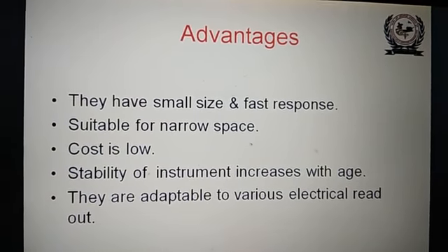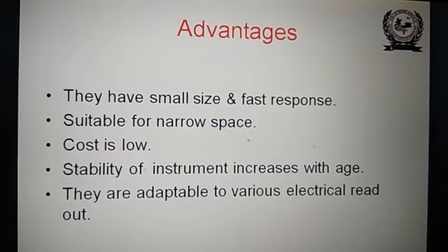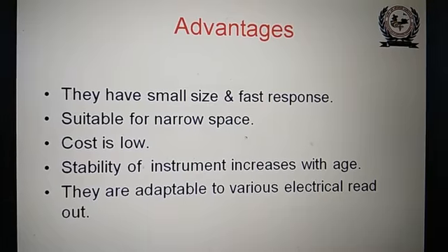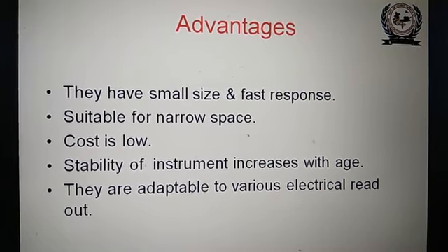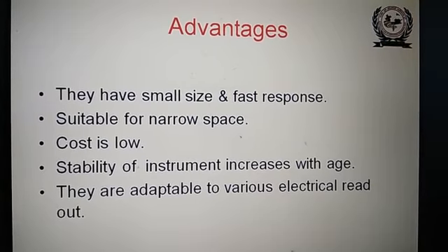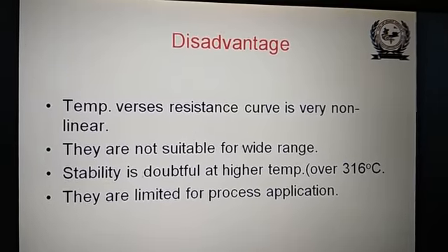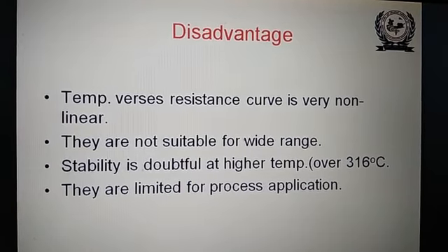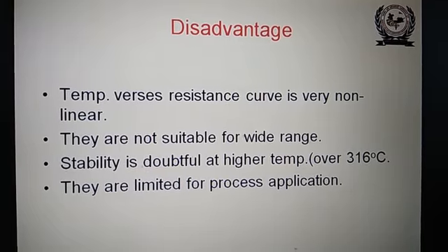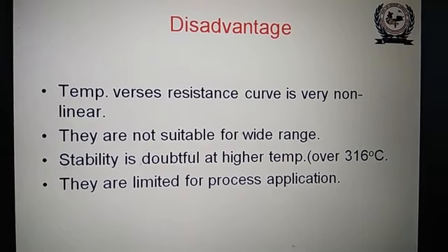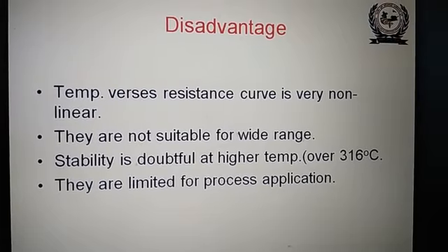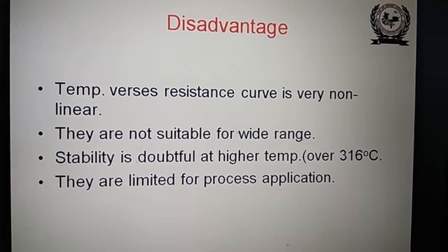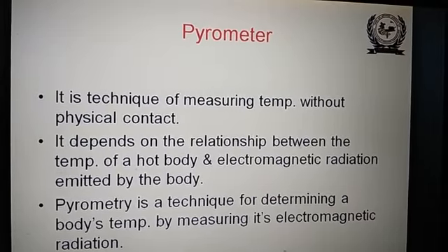Advantages: they have small size and fast response, suitable for narrow space, cost is low, stability of instrument increases with age, and they are adaptable to various electrical readouts. Disadvantages: the temperature versus resistance curve is very non-linear. They are not suitable for wide range. Stability is doubtful at higher temperature, over 316 degrees centigrade. They are limited for process applications.